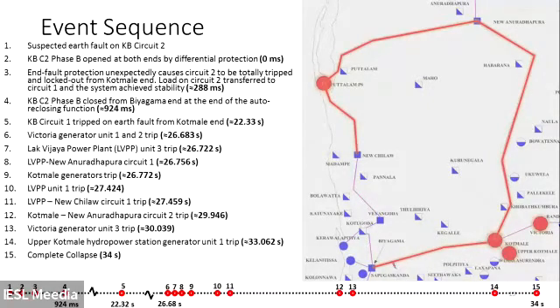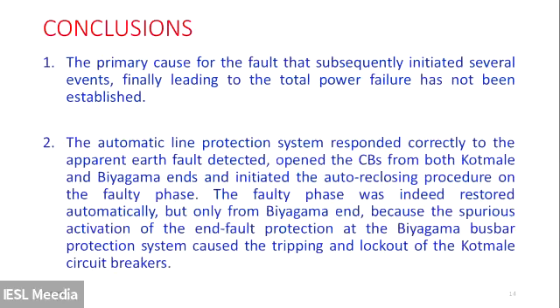Now, after going through the various reports from the CEB and also our visits to various relevant places, this is what we concluded in the report. The primary cause for the fault that subsequently initiated several events, finally leading to the total power failure, has not been established. The cause may be on the primary side, but the exact cause, how and why this earth fault happened, is not known.